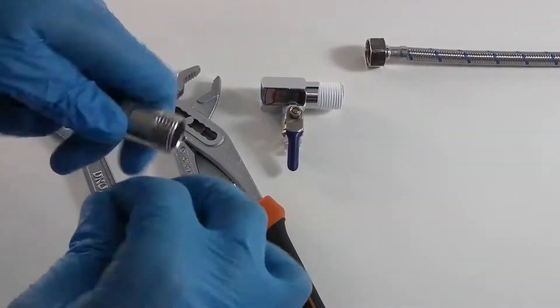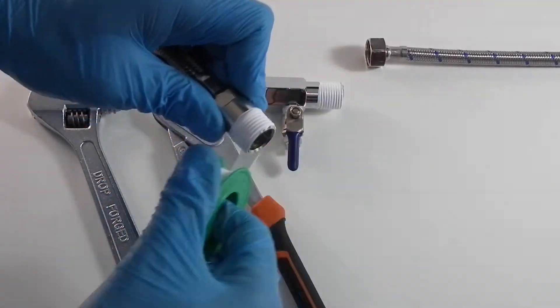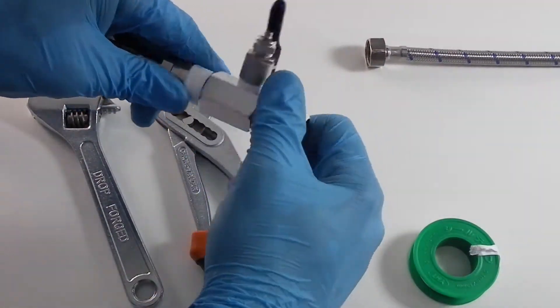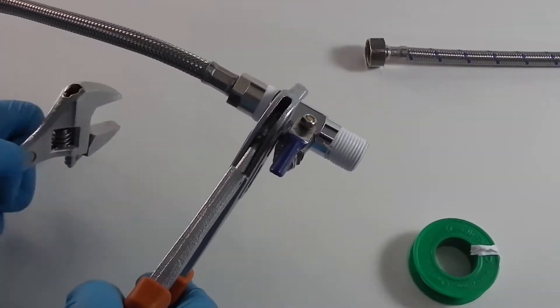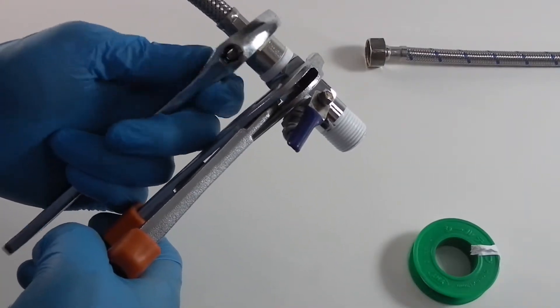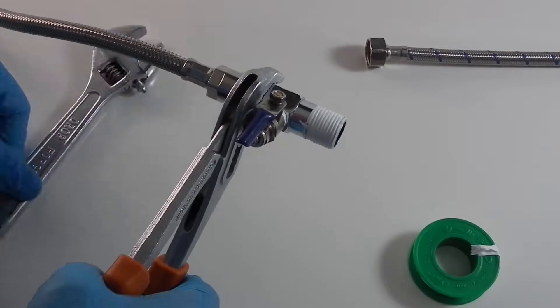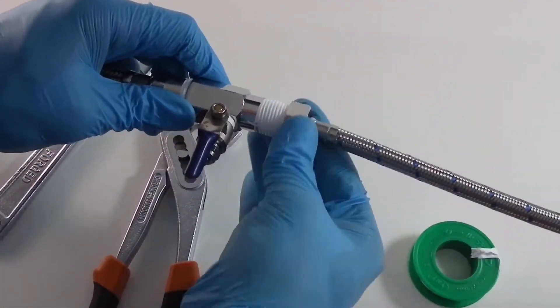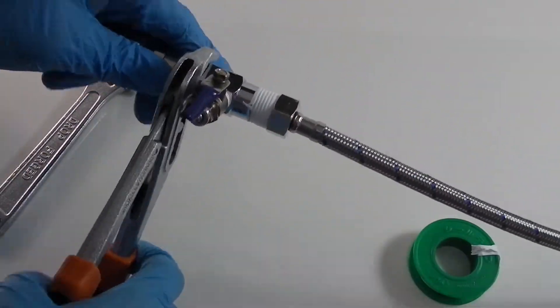Now we will fit the diverter valve between the main cold water feed, which normally has a 1/2 inch male thread connection, and the cold water line with 1/2 inch female thread to the sink. Make sure to use PTFE tape on the male thread to make the connection watertight. You can use the spanner to support the diverter valve while tightening connections with the wrench.